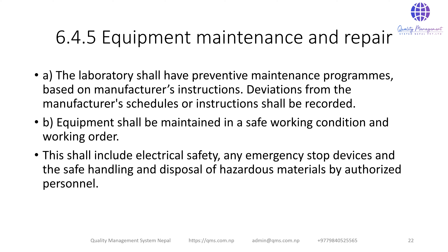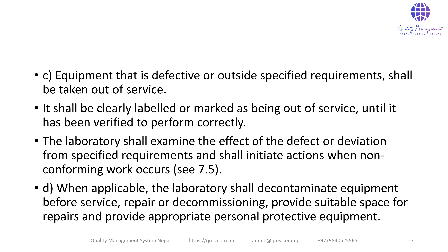6.4.5 Equipment Maintenance and Repair: The laboratory shall have preventive maintenance programs based on manufacturer instructions. Deviations from the manufacturer's schedules or instructions shall be recorded. Equipment shall be maintained in a safe working condition, including electrical safety, emergency stop devices, and safe handling and disposal of hazardous materials by authorized personnel. Equipment that is defective or outside specified requirements shall be taken out of service and clearly labeled as out of service until verified to perform correctly. The laboratory shall examine the effect of any defect or deviation and initiate corrective actions for non-conforming work. When applicable, the laboratory shall decontaminate equipment before service, repair, or decommissioning.